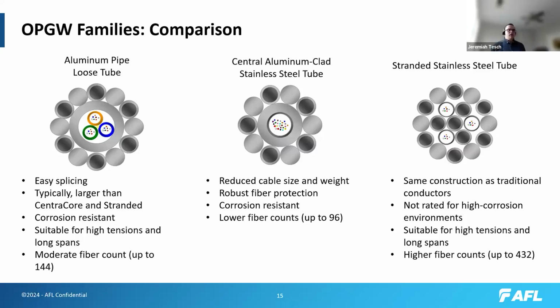This is suitable for high tensions and long spans. Typically, if a customer asks me for a solution and they have a very long span, maybe a 4,000-foot river crossing, I would typically use the stranded design because you can add in more wires and extra strength. You could certainly make solutions with all three of these. You can actually add additional layers of wires to any of them, but we do typically end up using the stranded style for extra long spans. This can also hold the highest potential fiber count. Our designs typically can hold up to 432 with the standard 250 micron fiber.